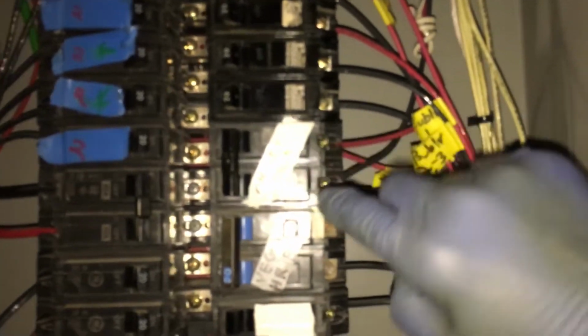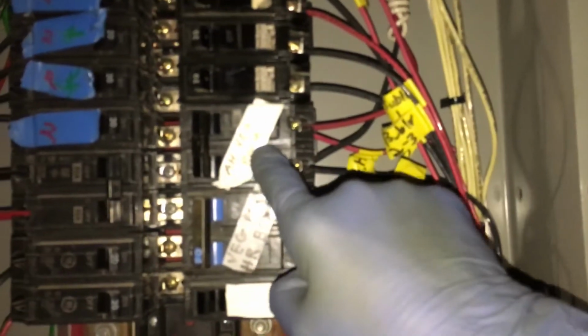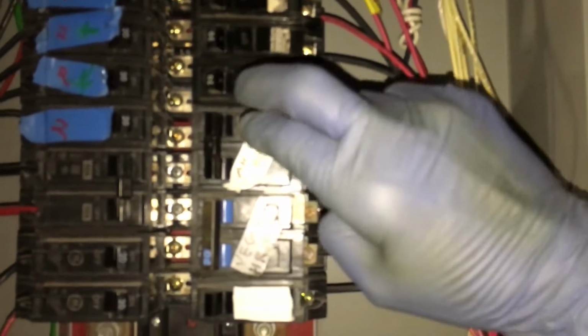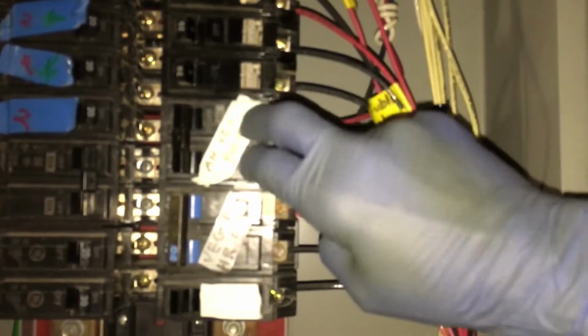So he double piggybacked off of one circuit breaker. It's a motor, it's actually a pump, a water pump. It's a 10 amp pump, and this is a 20 amp breaker. It has a 10 amp pump, but it's also sharing with an air handler. Two air handlers. So we got two air handlers that draw almost 6 amps apiece, so there's 12. We have an inductive hard start that has an inrush current of 10 amps.